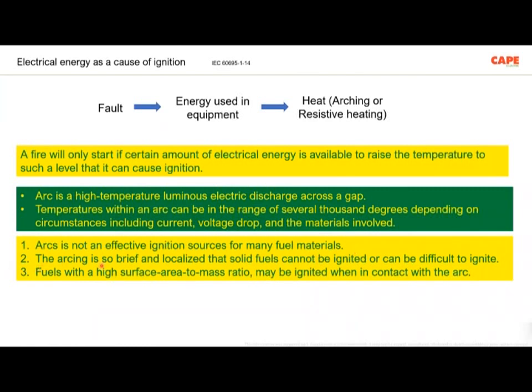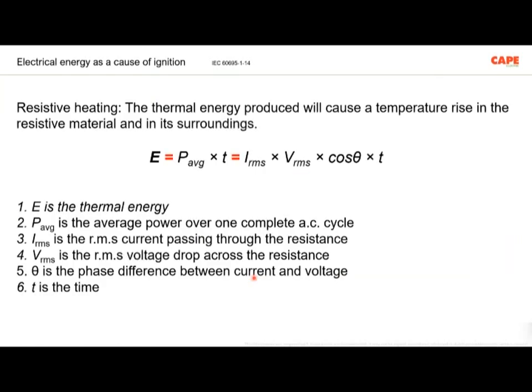Continuous arcing is also considered. The arcing is so brief and localized that solid fuels cannot be ignited or are difficult to ignite. Fuels with a high surface area to mass ratio may be ignited on contact with the arc. So if we think that an arc is creating a fire, then we have to consider the other situations as well. An arc as such cannot ignite fire, provided there are no combustible things nearby. Most of the time, resistive heating is creating the failure or the fire. For resistive heating, the standard establishes how to calculate it, what energy is involved, what duration is involved, and how much energy and for how long the equipment can withstand. All these things are very well documented, and can be used for investigation and failure analysis.